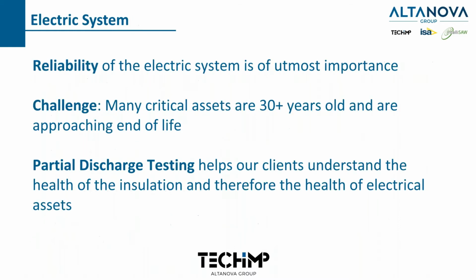All right, so let's talk about why partial discharge is important. I think we all know reliability is important, so we don't need to discuss how important reliability is. So what's the challenge out there? Well, of course, the challenge is that assets age. And as they age or approach the end of life, insulation breaks down, and that's where partial discharge comes in. It helps you understand the health of the insulation, and therefore the health of your electrical assets. Helps you determine what needs to be replaced or repaired, and also sometimes more importantly, what doesn't need to be replaced or repaired.